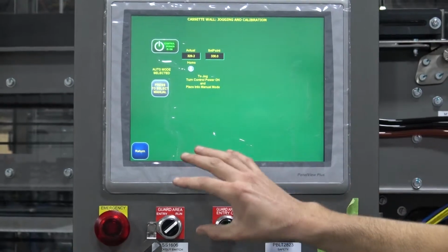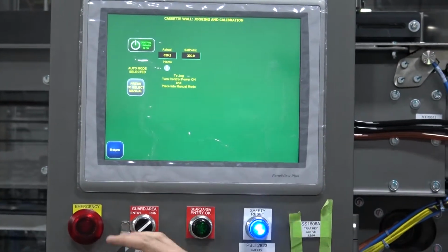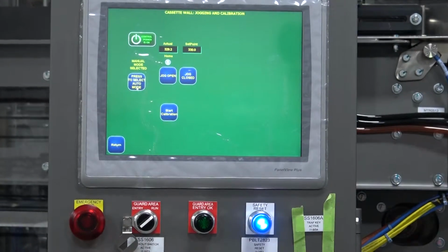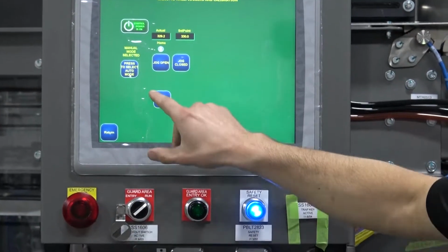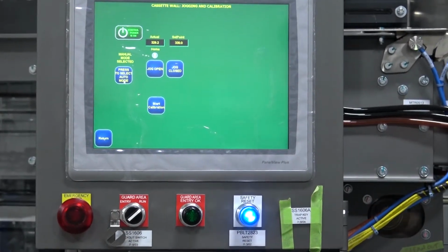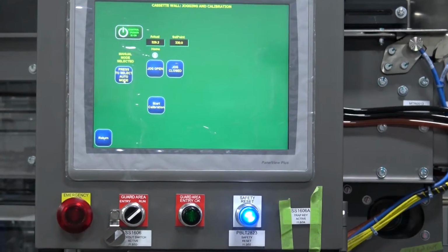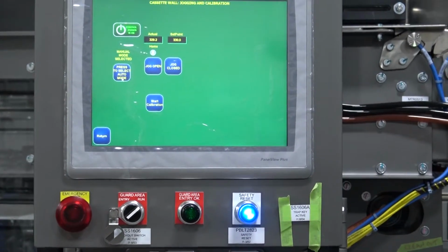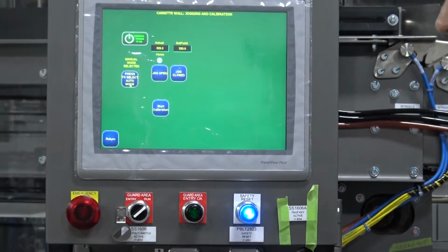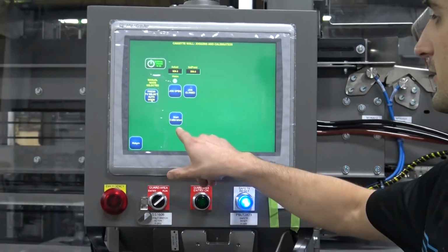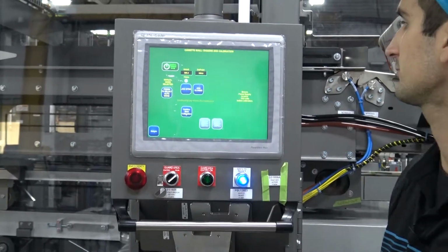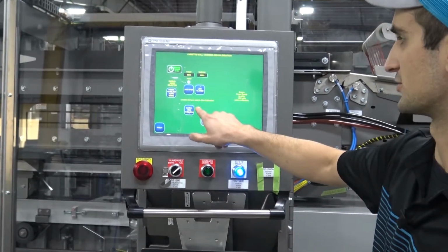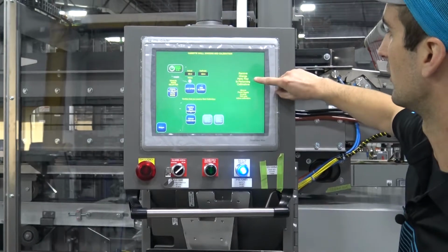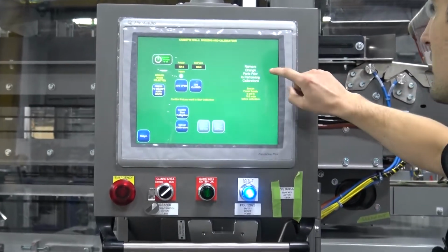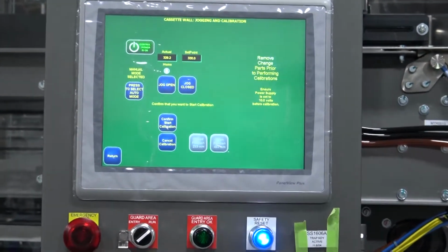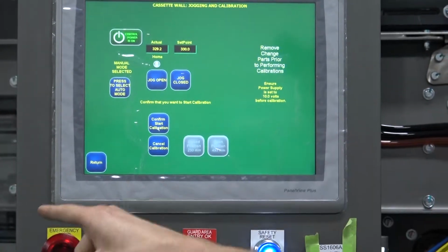So I want to enter the manual mode to do the calibration. Press select manual, and right now I get manual controls. I can jog that with open or close. When you use that, be careful that the lift plate's not in there, or you're going to close the cassette wall on the lift plate. You can do that in this mode, so use it with caution. Next we're going to start calibration. And then it's going to give you a warning message, are you sure you want to start the calibration? And also remove the change parts prior to performing the calibration, so again we don't collapse on the change parts. So I do need to do that.